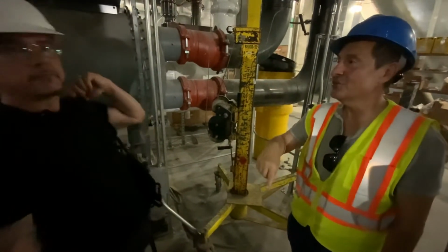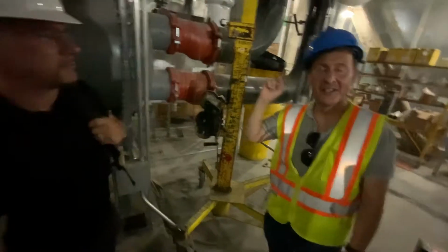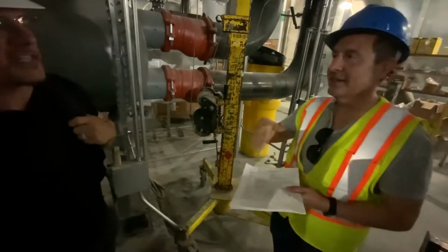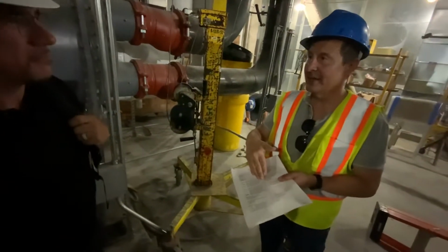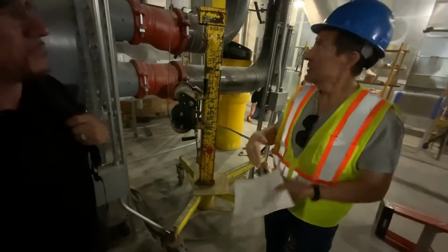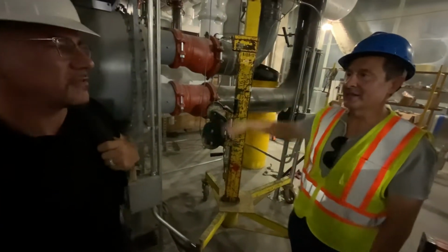And the reason why you do that is because these big valves right here, can you say that on the video? Yep. Those valves, when they open, they're not linear. If they open up a little bit, it's a huge gush of water. So if that valve opens while that machine's running, what's going to happen to the flow through the running machine? It's going to disappear.